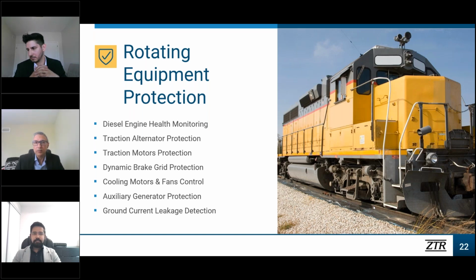Here we're talking about voltage protection to prevent flashovers, current regulation to prevent thermal damage to the motors, and stall detection to prevent damage to the commutators in DC motors. Stall detection applies when a DC motor locomotive is stalled on a grade, not moving, under heavy load, with a lot of current going through the brushes and commutators which aren't moving - this results in permanent damage to the commutator bars.